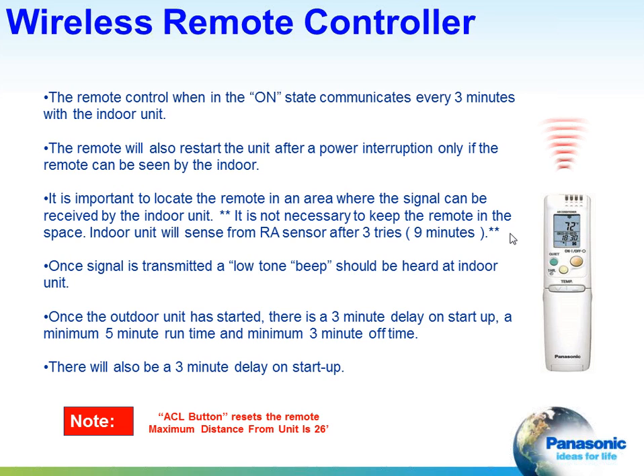And it's important to locate the remote in an area where the signal can be received by the indoor unit. This is an infrared controller, so you have to have line of sight. Think line of sight here. You have to have a clear path from the remote control to the indoor unit so the signal can be received by the indoor unit, and so the control can see what the indoor unit is doing. Once the outdoor unit is started, there's a 3-minute delay on startup of the indoor unit. That's to allow the indoor coil to reach the cooling temperature that's desired, or the heating temperature that's desired.